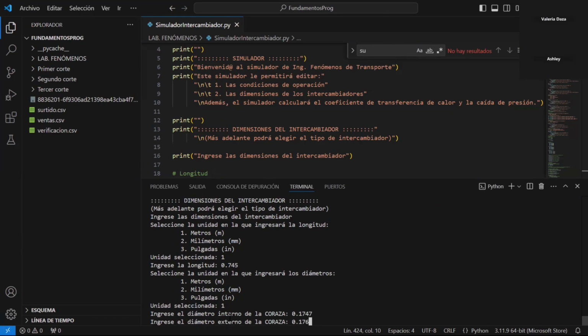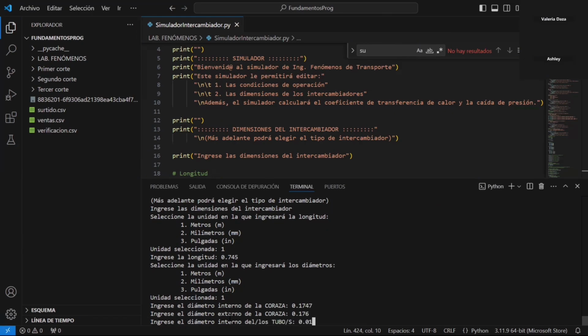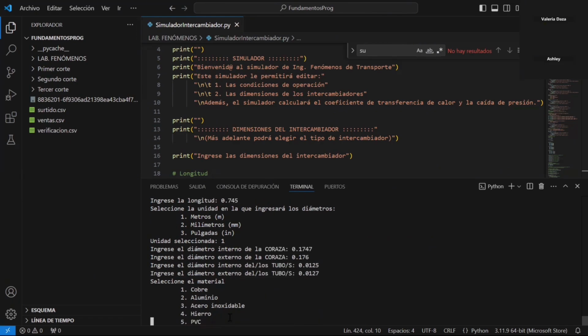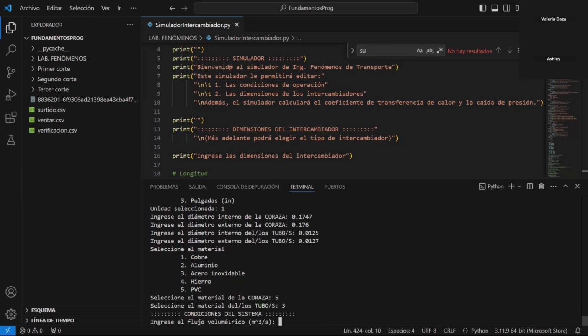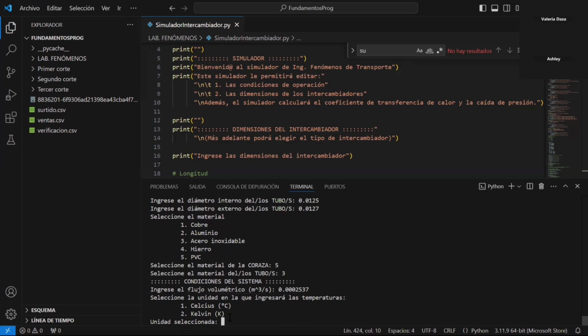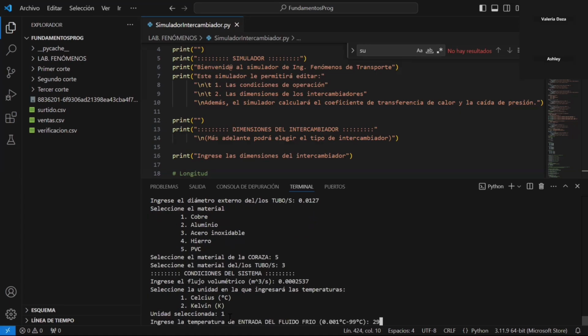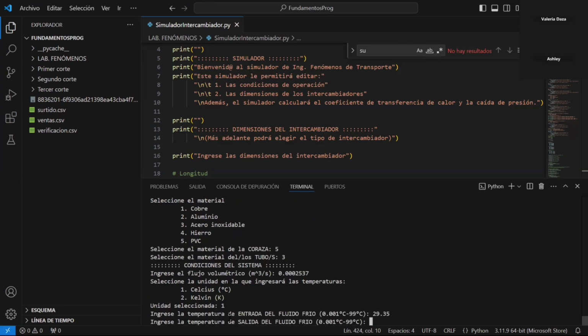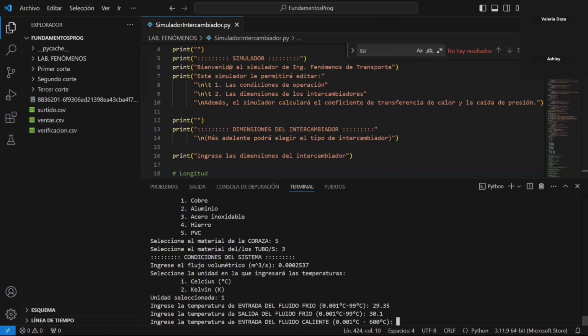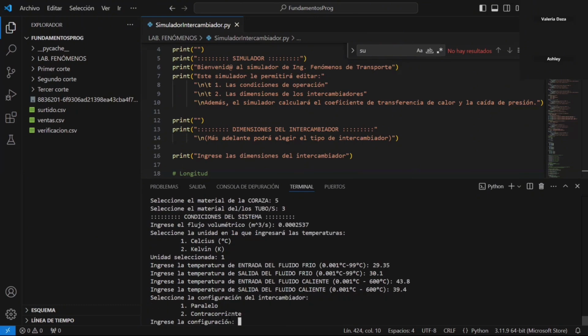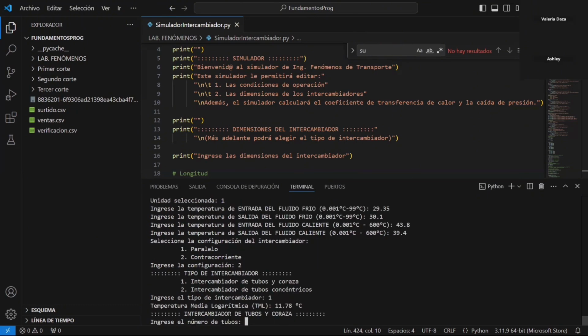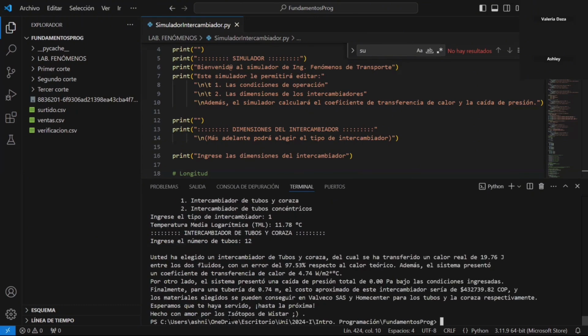For example, the units of the length, the units of the diameters, and each diameter, internal and external, of each tube or shell, and then the material of each of those. Then they have to enter the flow and then the inlet and outlet temperatures of each fluid. The tool is intuitive for the user so they can understand what they are doing. Then the configuration, and finally the type of exchanger and the number of tubes, for finally getting this answer.